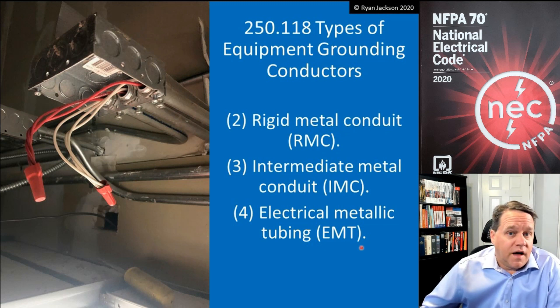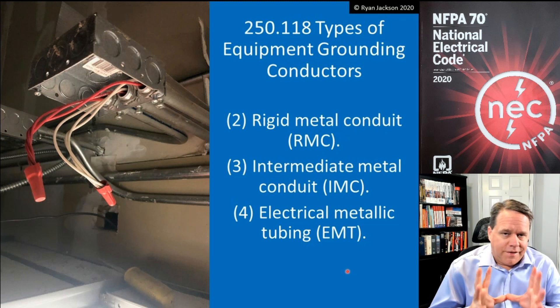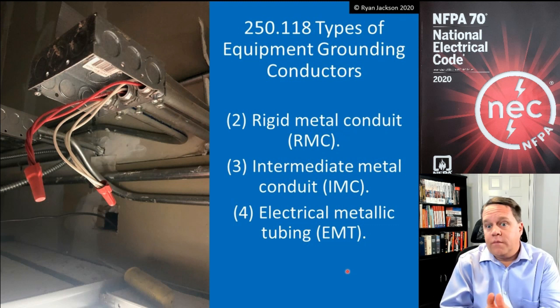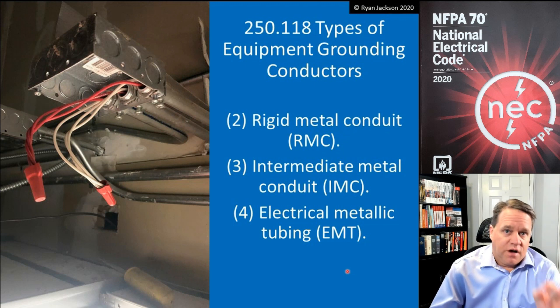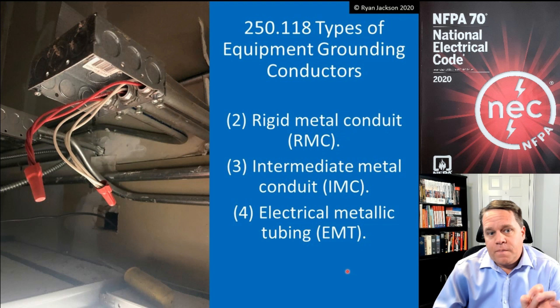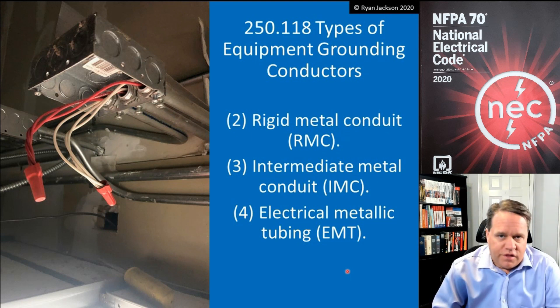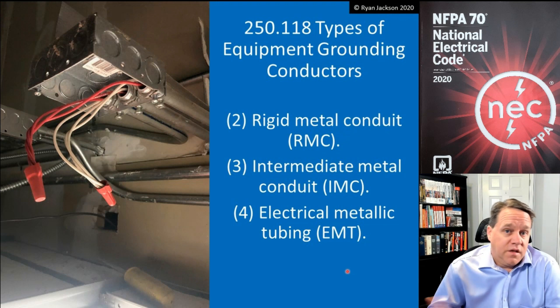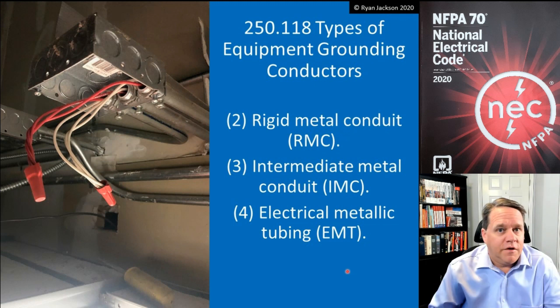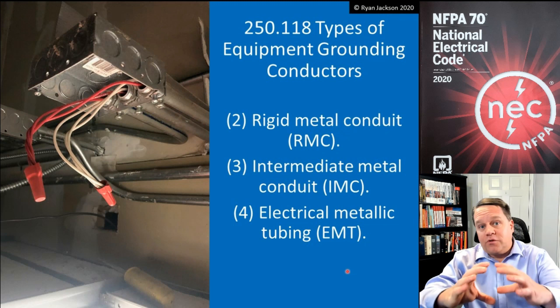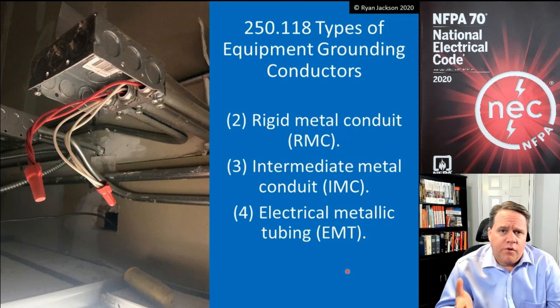I'm going to say something that's going to bother a lot of people, but it's a fact: a metal raceway — EMT, RMC, or IMC — is actually a better equipment grounding conductor as it relates to the science. The impedance of those raceways is much lower than the impedance of a green or bare copper conductor. I know steel is not as good a conductor as copper, but a giant piece of steel is a better conductor than a tiny piece of copper. Which has less resistance: four-inch rigid or 14-gauge copper?